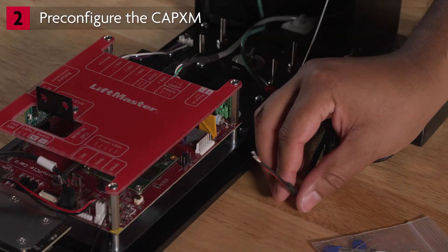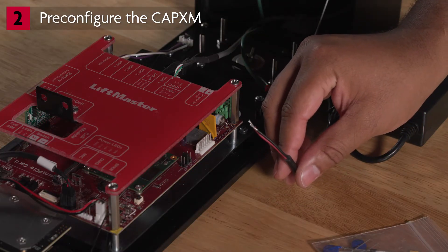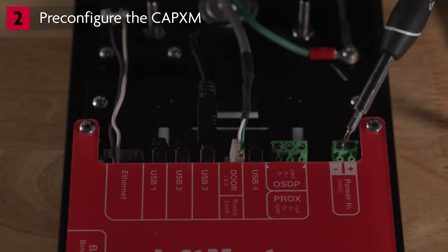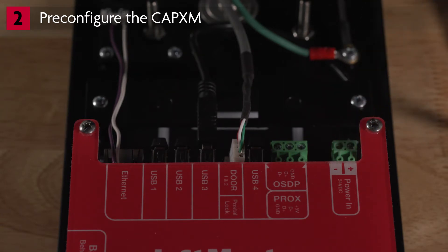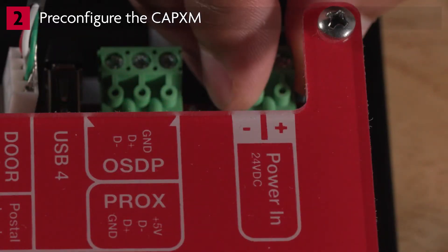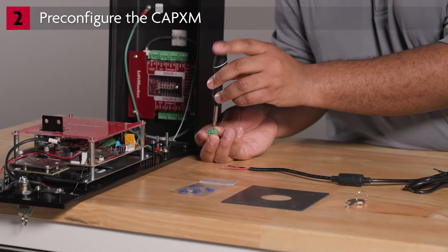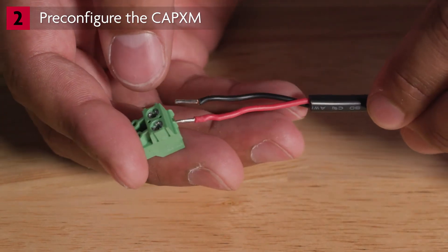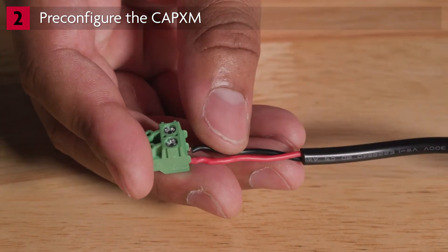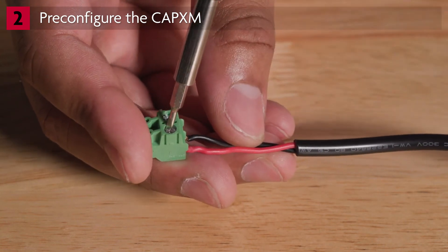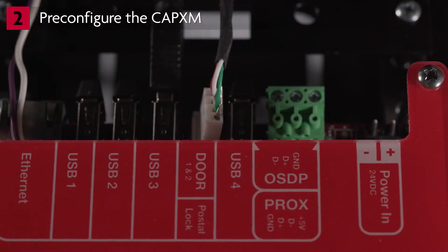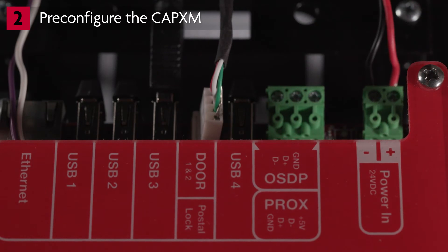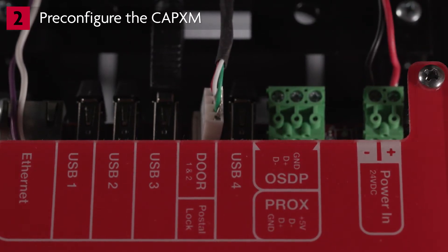Locate the power supply and observe the stripped and tinned red and black wires. Locate the power input connector on the control board. Notice the markings showing plus and minus and observe the orientation of the terminal block. You need to make sure you connect wires for the correct polarity. Remove the terminal block and loosen the screws. Insert the red wire into the terminal block hole that aligns with the plus terminal on the board. Insert the black wire into the other hole and tighten the screws to secure the wires. Reattach the terminal block to the power input connector, making sure the red wire aligns to the plus terminal and the black wire aligns to the minus terminal.